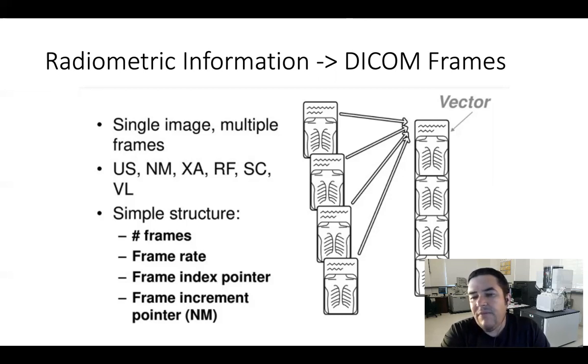The thing is that once you put the temperature matrix, it's not a traditional DICOM file, and it would be hard for those free DICOM readers to read those files. So once we have the radiometric information in the DICOM file, we need to develop our own viewer, so that viewer knows that thermography file in one of the frames has the radiometric information. So that the reader gets that radiometric information, displays it, and then you can do whatever you want with it.